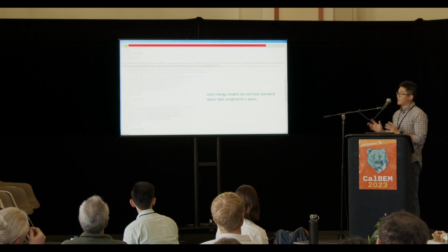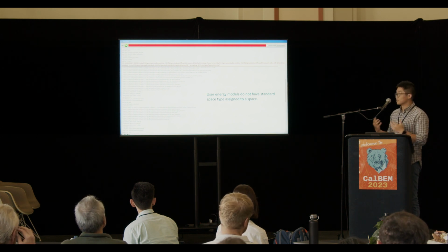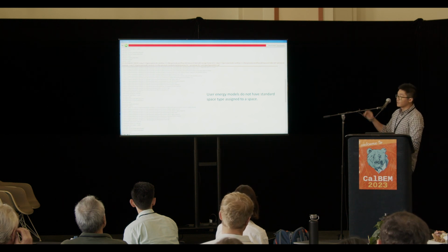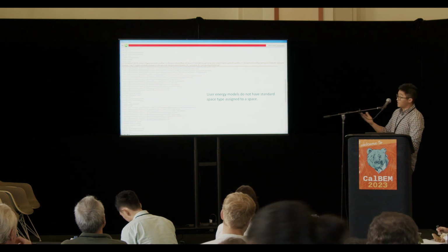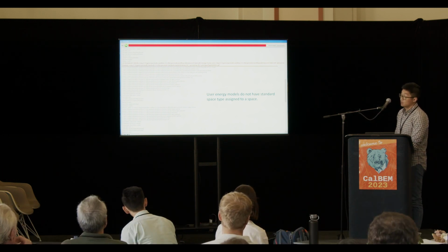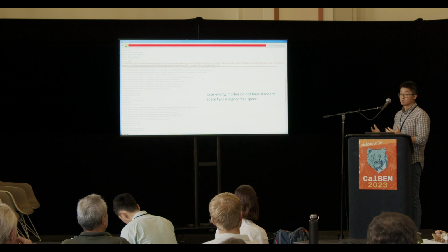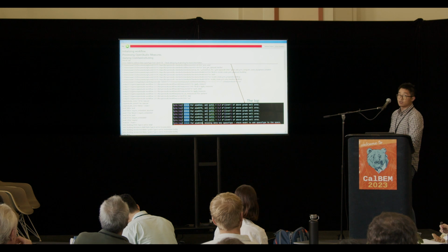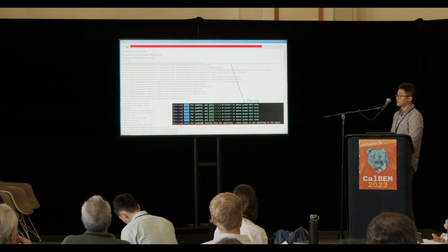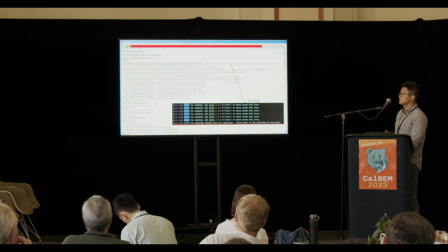But trust me, this is not some hacking message. It's basically a message from Ruby telling the user that there's data it's looking for, but it's not there. In the energy modeling context, it means a space type is not defined for that space. But the message is not very helpful, and even in the automation process, it's hard to actually predict the space types. So what we did was to simply let it fail. We give a much clearer message to tell the user, hey, you need to put the space types into your spaces. So the user is happy because he knows what to do now, and he successfully ran the PRM measure.